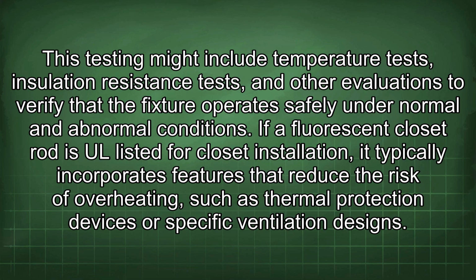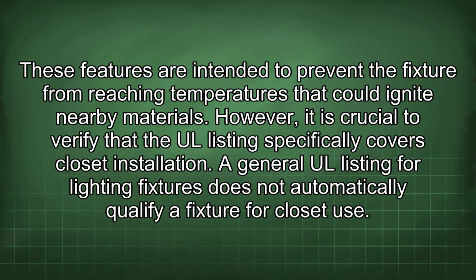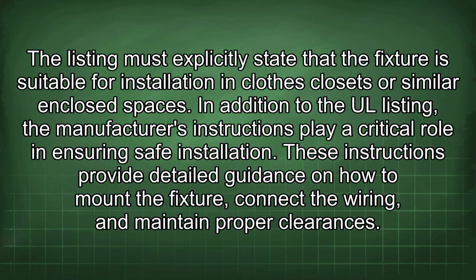This testing might include temperature tests, insulation resistance tests, and other evaluations to verify that the fixture operates safely under normal and abnormal conditions. If a fluorescent closet rod is UL listed for closet installation, it typically incorporates features that reduce the risk of overheating, such as thermal protection devices or specific ventilation designs. These features are intended to prevent the fixture from reaching temperatures that could ignite nearby materials. However, it is crucial to verify that the UL listing specifically covers closet installation. A general UL listing for lighting fixtures does not automatically qualify a fixture for closet use. The listing must explicitly state that the fixture is suitable for installation in clothes closets or similar enclosed spaces.